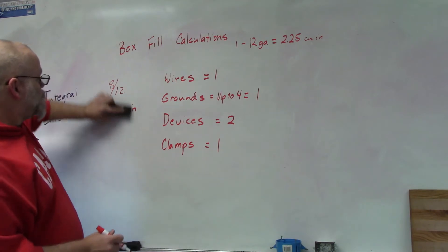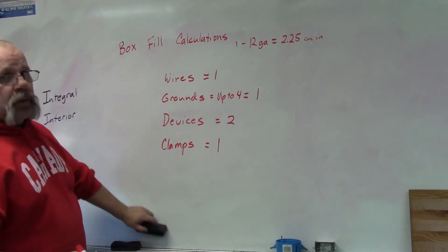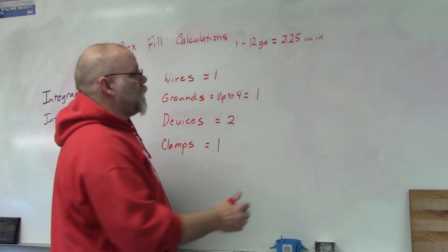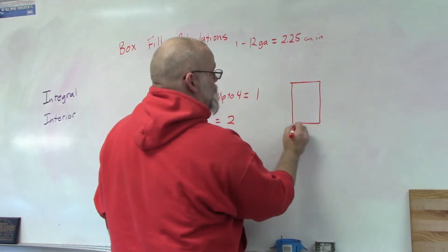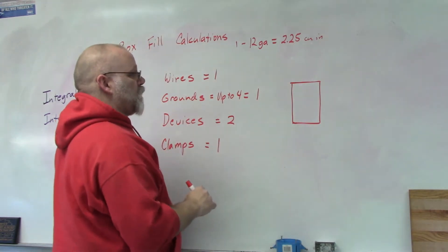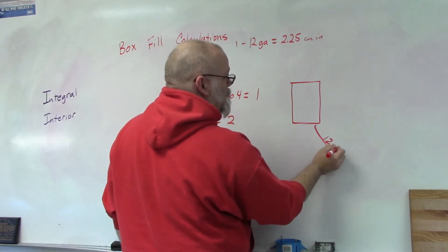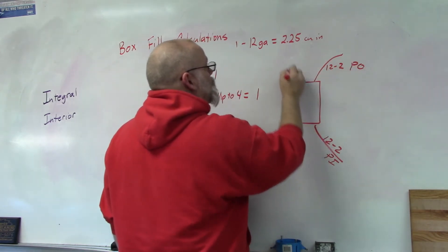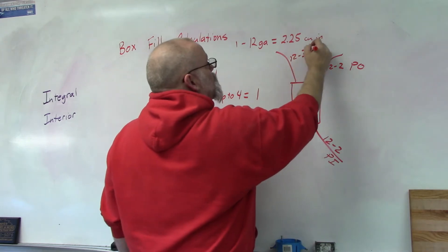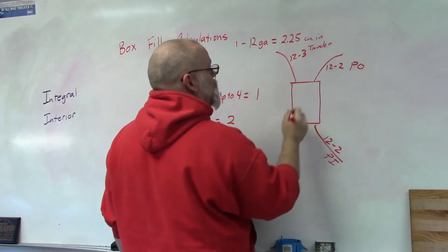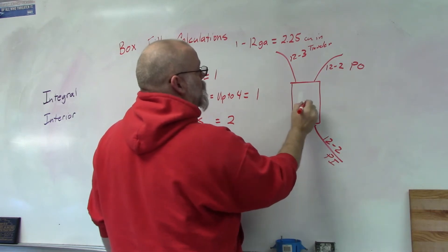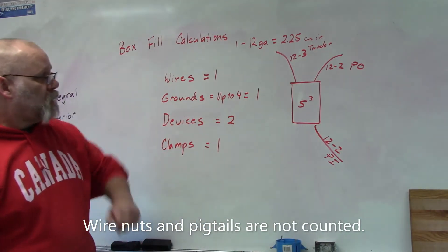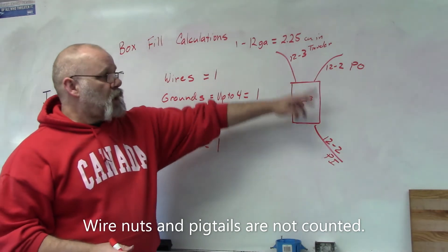So let's give an example of a box and then we can determine what size of a box you would need. Here's a standard single-gang box with a 12-2 power in, a 12-2 power out, then it has a 12-3 traveler. So we're going to put a three-way switch in here. So how big of a box do we need for these wires to fit into it?